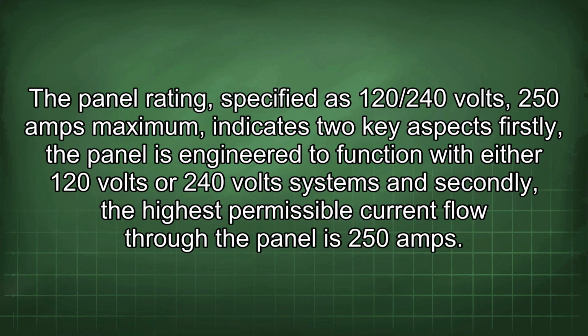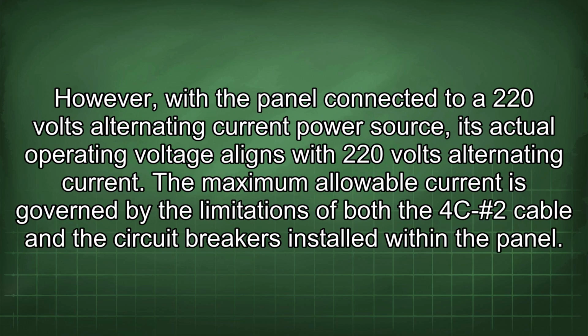The panel rating, specified as 120/240 volts, 250 amps maximum, indicates 2 key aspects. Firstly, the panel is engineered to function with either 120 volt or 240 volt systems, and secondly, the highest permissible current flow through the panel is 250 amps. However, with the panel connected to a 220 volts alternating current power source, its actual operating voltage aligns with 220 volts alternating current. The maximum allowable current is governed by the limitations of both the 4C-2 cable and the circuit breakers installed within the panel.